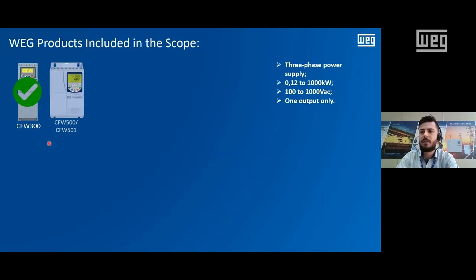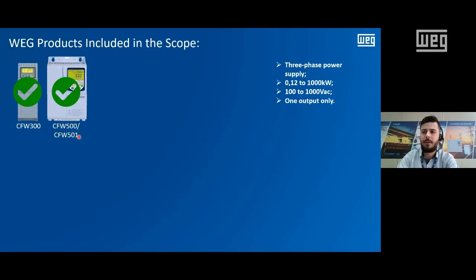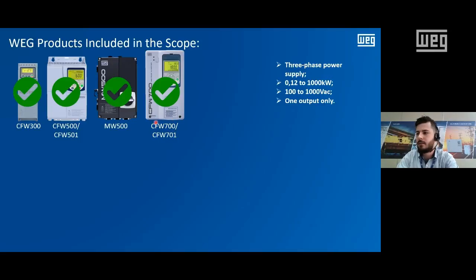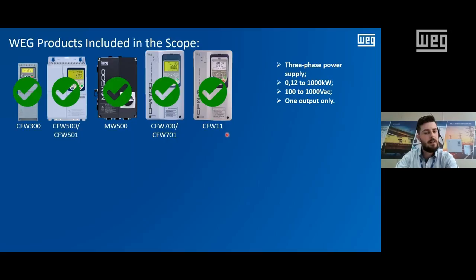Now that we understand the scope of the regulation, let's talk about which WEG products are included in the scope. Just to remember, the products included in the scope have a 3-phase power supply from 0.12 to 1000 kilowatts, from 100 to 1000 volts, and have only one output. Well, we have our mini drive, the CFW 300, included in the scope. The CFW 500 and its variations, such as the HVAC drive, are included in the scope. The decentralized drive MW 500 is included in the scope. The CFW 700, the CFW 701 and the CFW 11 are also included, as well as their variations, because we have some variations with high protection degrees. They are all part of this scope.